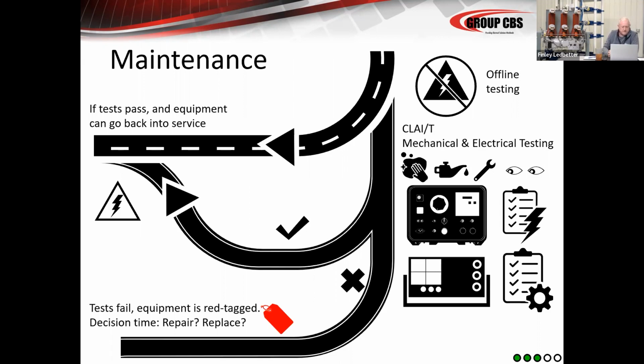I guess I don't remember where we were at, but we're coming out of the second life cycle. Now we're talking about maintenance after the equipment is 30, 40, 50 years old. At that point, you start to see some red tag operations for wear because the breakers are wearing. You start to see situations where they have a lot of operations on them.